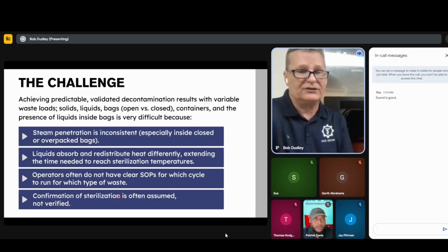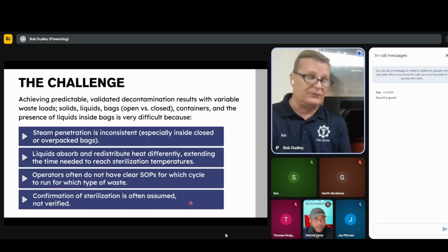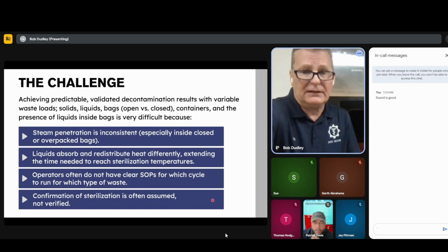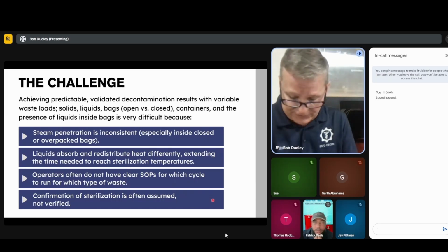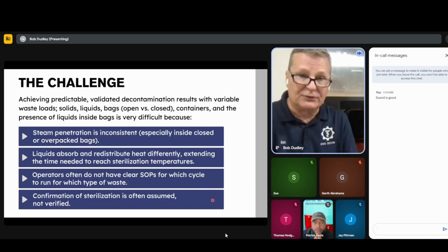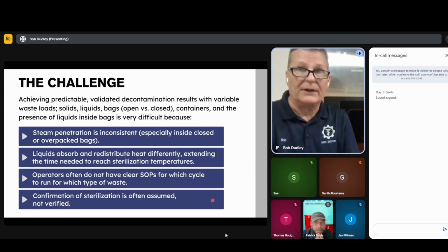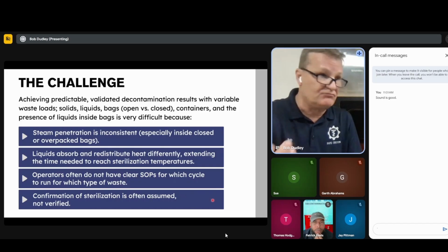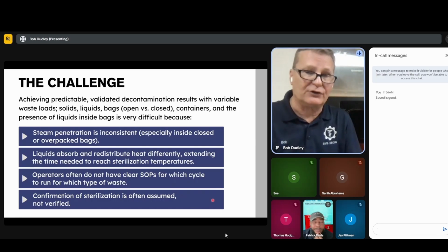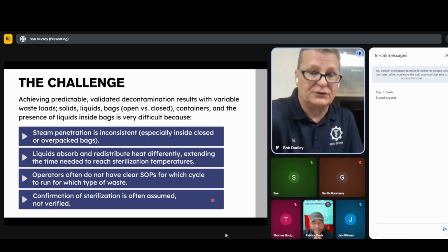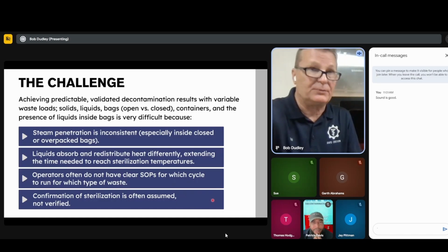The confirmation of sterilization is generally either done with a chemical heat strip, which we will go over, or the biological indicator. Now, the biological indicators, and this comes from absolute experience, are not placed in a proper position. And the reason is, who wants to go digging around in biohazardous waste to retrieve their biological indicator? Everybody fusses about it. It's gross, especially when you're dealing with animal waste, animal bedding, and stuff like that.